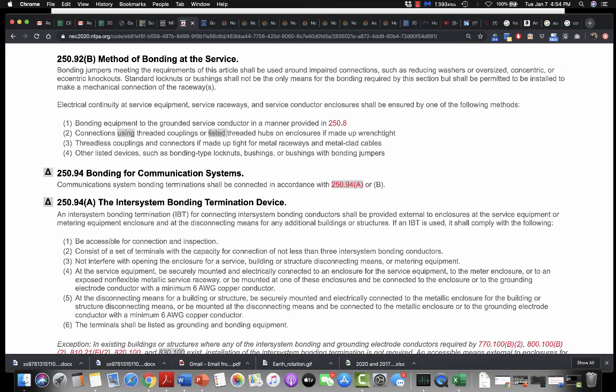Connections using threaded couplings or listed threaded hubs on enclosures, if made up wrench tight. So you've got to look out for your threads and make sure that the threads are right. Threadless couplings and connectors, if made up tight, for metal raceways and metal-clad cables. Other listed devices. So we just need to make sure that we're using devices that are good enough. But a lot of times, to bond it, you can just use a piece of copper. That's a pretty good way to bond at the service, a piece of copper.